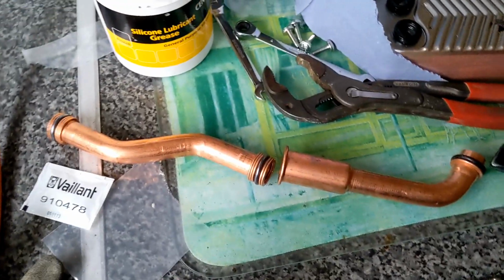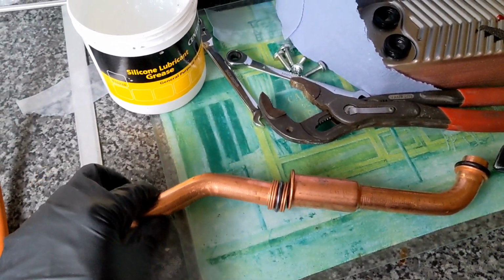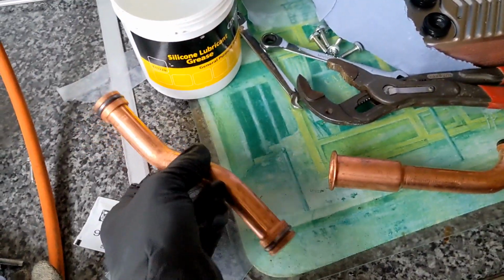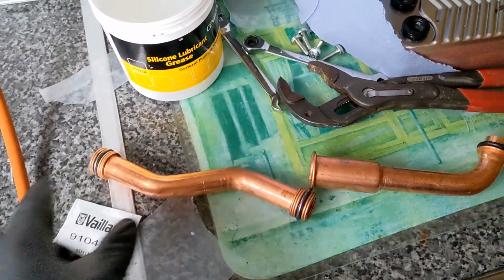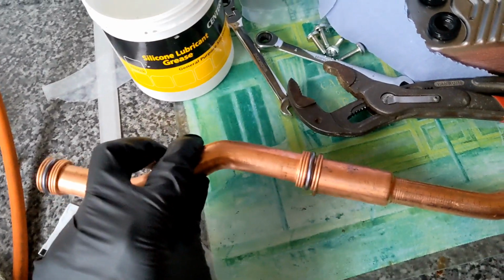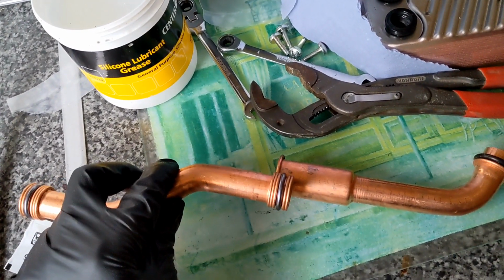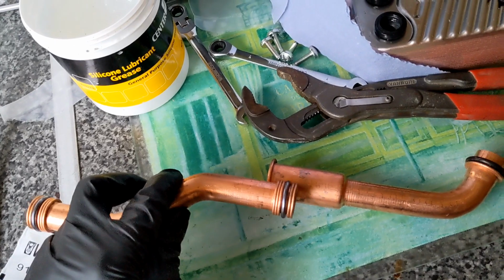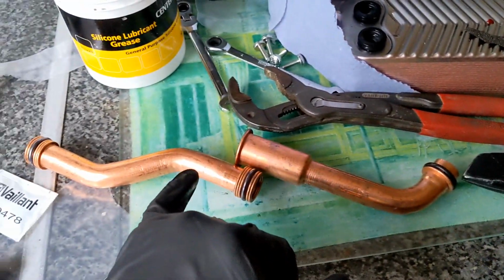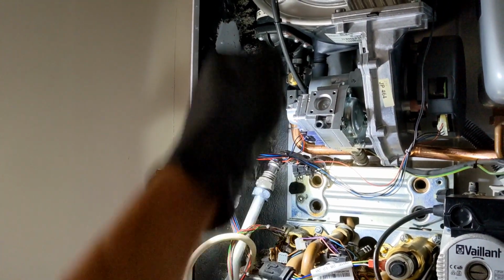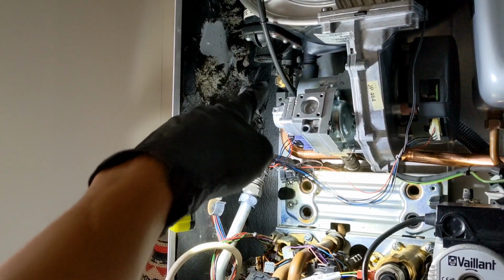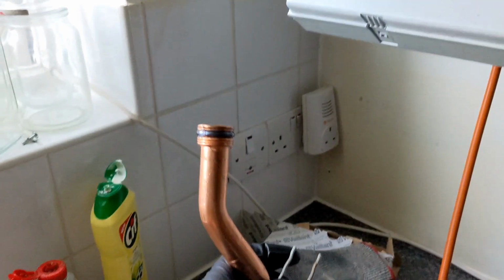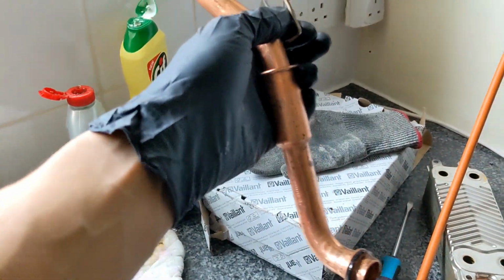Right, so the new flow copper connection, it comes as a slip joint. So this doesn't matter whether it goes around like that or it's like that. The orientation is exactly the same. But what happens is this will go into the bottom part there, and you can push it all the way down and slide it up. So what that does is when you get it into there, you can pop the bottom side in first, have that slid down. You can then get it into position and then pop it straight into the main heat exchanger connection. Right, that's all greased up. There's a slip coupling, the slip joint there.